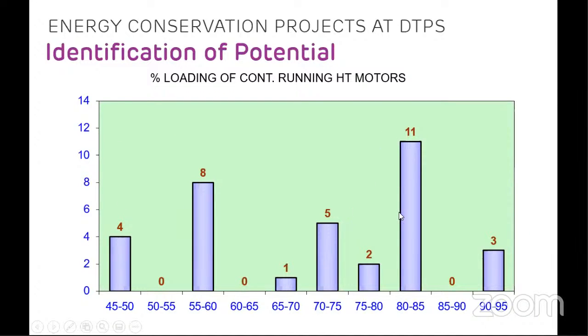So there were 11 motors which were loaded 80 to 85% of their rated design. Suppose the rated design of the motor is 100 kilowatt, it is only running at 80 or 85 kilowatts. 11 such motors were identified. Only 3 motors were running at their full capacity. The rest of these motors are running at lower capacity than their design. So all of these have a very good benefit if a VFD is installed on these motors, especially ones having loading lower than 80%.